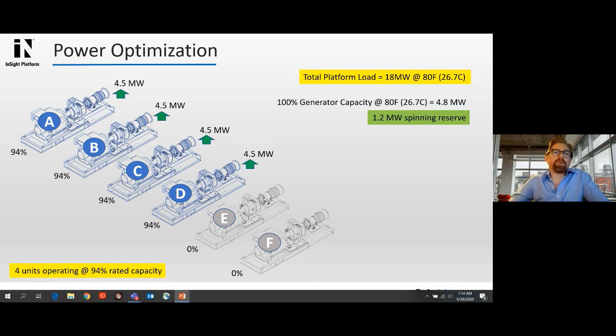Now, I think most could quickly identify that if we were to reduce down to 5 units, we would still be operating with 5 units, each at 75% capacity, generating 3.6 megawatts. Even with 5 units in operation, the customer still has 6 megawatts of spinning reserve capacity should the platform load have any sudden increases. And in fact, given the size of the engines and the capability of them in this instance, we can actually reduce it all the way down to 4 units in operation. So each of the engines is operating at 94% of their capacity, generating 4.5 megawatts apiece. Even in this scenario, we still have a 1.2 megawatt spinning reserve available to maintain reliable power on this platform.